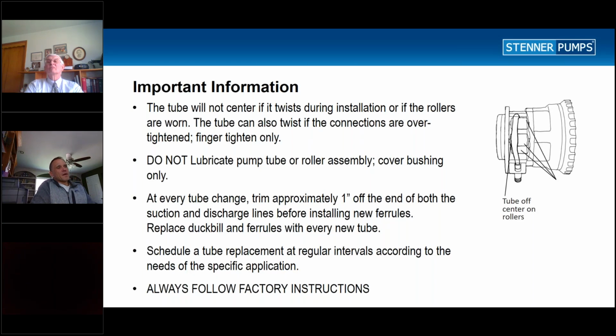So I want to go back here. A couple of things that they don't point out here that I feel are important, and it's better if I just review it with everybody. When we're changing the tube, they mentioned run the tube with the rollers collapsed for about 2 minutes. If you're running a number 1 tube or number 2 tube, running the rollers collapsed before expanding will help exercise the rubber. That often works with the number 1 and 2 tubes, and that's usually adequate.